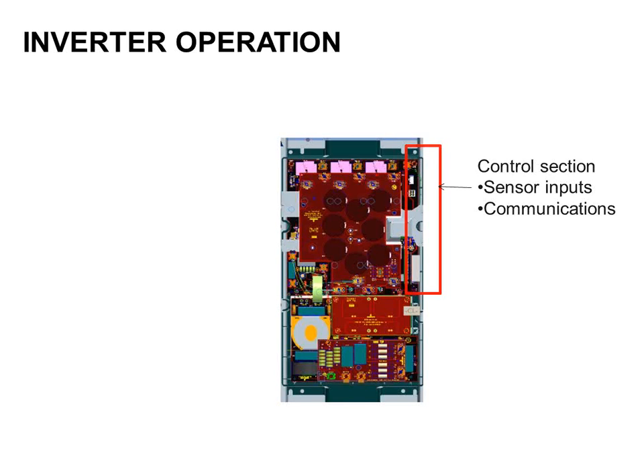So when you put a VFD on a fan motor, right, you have a converter that converts from AC to DC, then you modulate the signal, then you convert it back to AC and spit it out. In the case of these variable speed heat pumps, the idea is, well, why would I want to convert it again? Every time I convert it, I have heat loss and heat waste. Let's just get DC compressors and do it that way. So AC comes in from the power company, we change it to DC, we modulate the signal to the capacity we want, and we push that back out to the compressor.